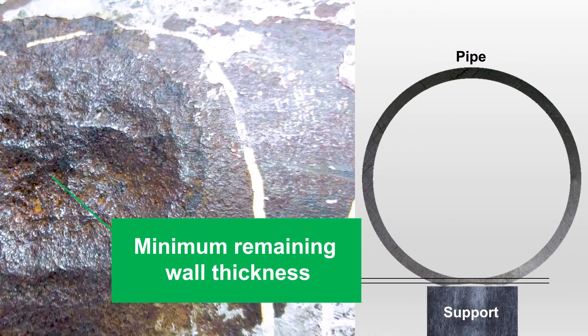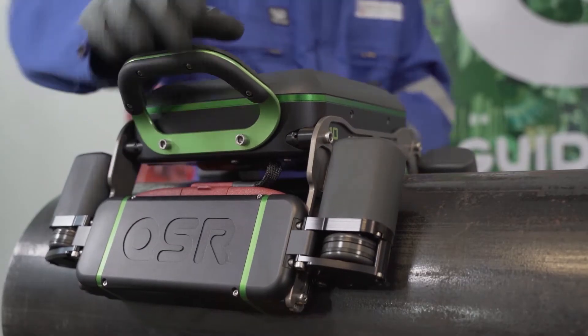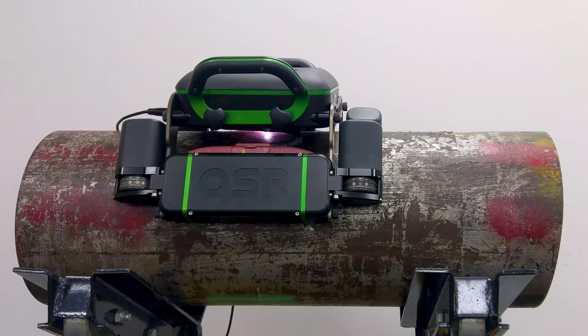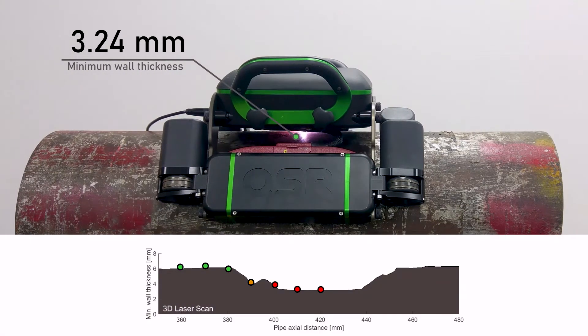So if you want to measure the minimum remaining wall thickness, then you need the QSR1. The QSR1 uses 3D laser scanning to accurately give the minimum remaining wall thickness along the pipe.